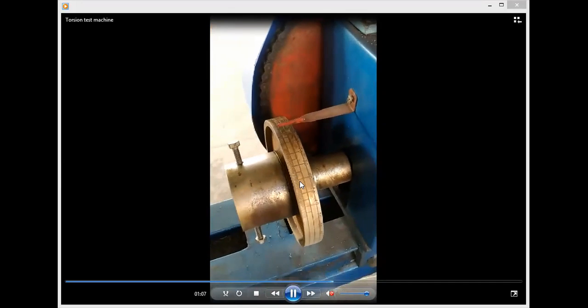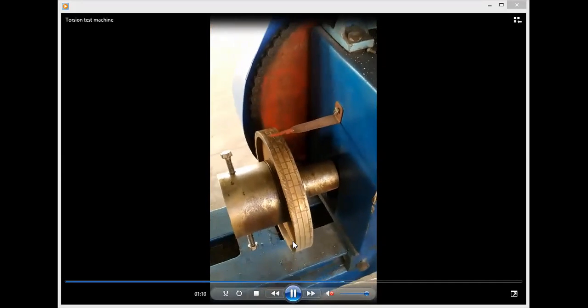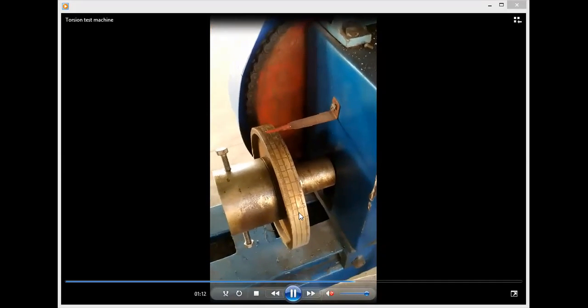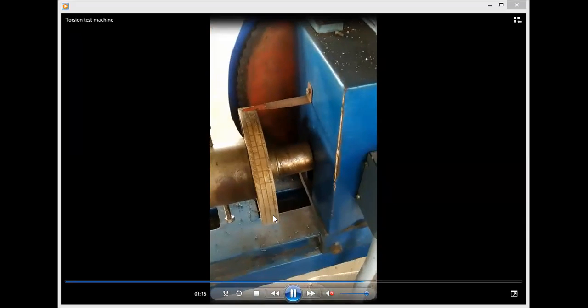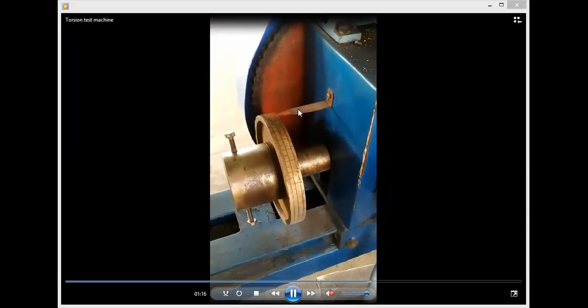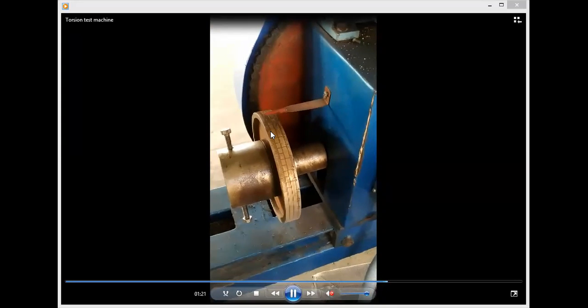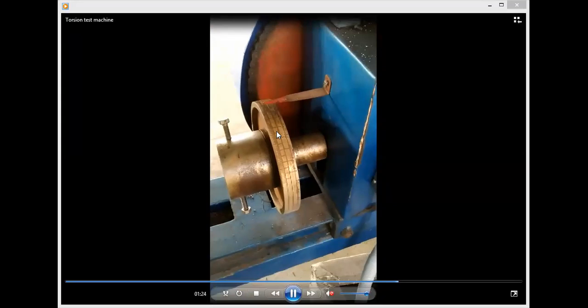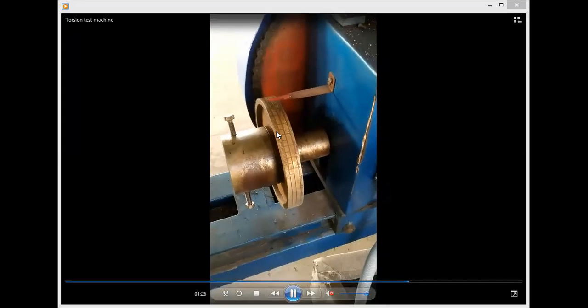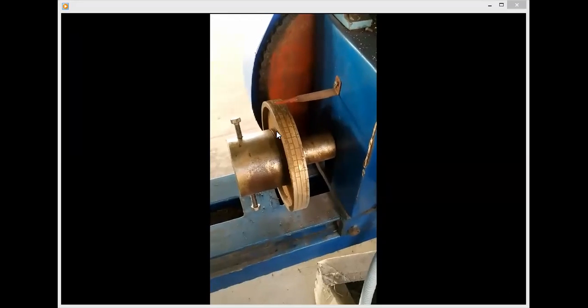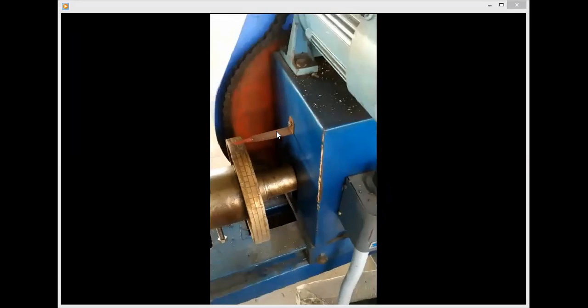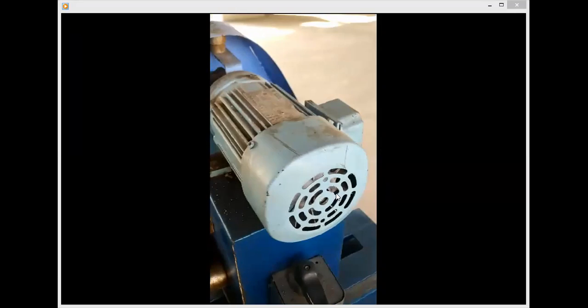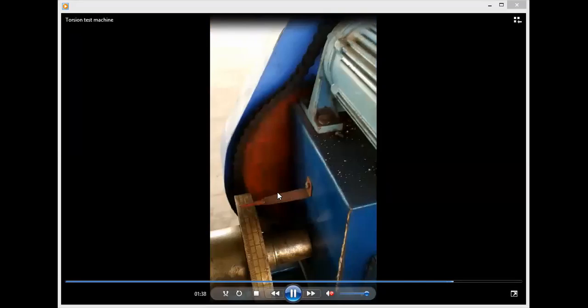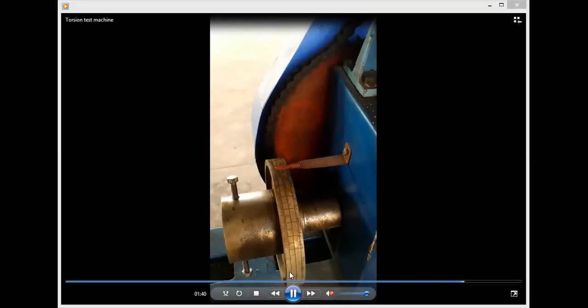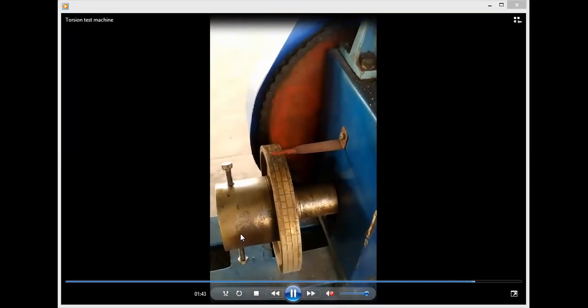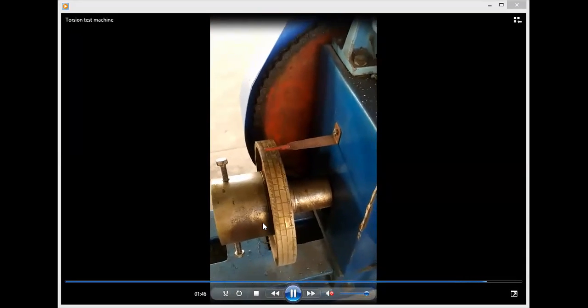This graduated scale gives a graduation of 0 to 360 degrees, and it will rotate. At the moment of breakage, the reading given by this will be the amount of rotation the workpiece twisted before breakage. Sometimes three or more complete twists are required to break it. Here is the motor itself, and this is a gear-driven wheel which runs this device, which is the one-side holder of the torsion testing bar.